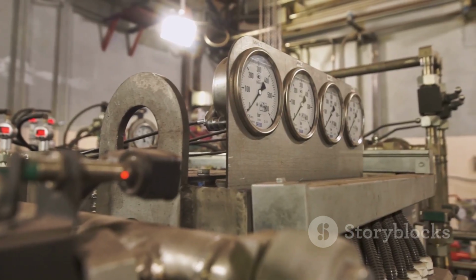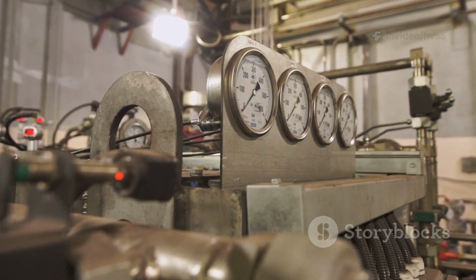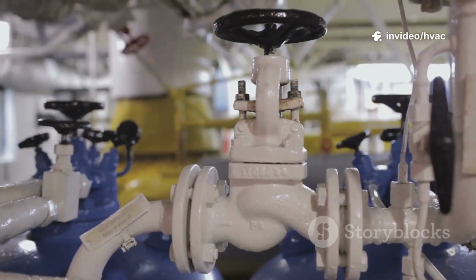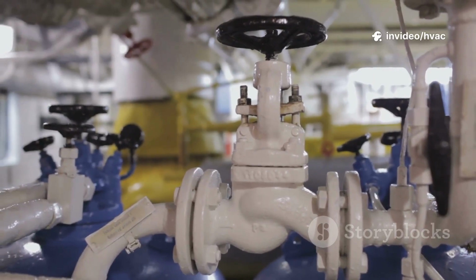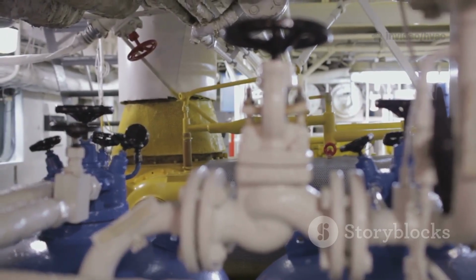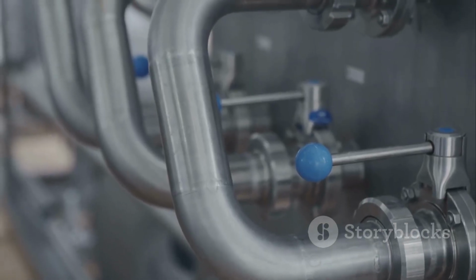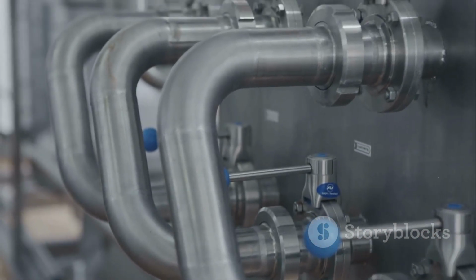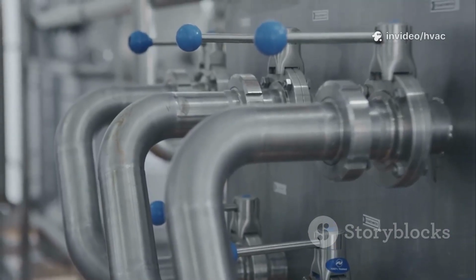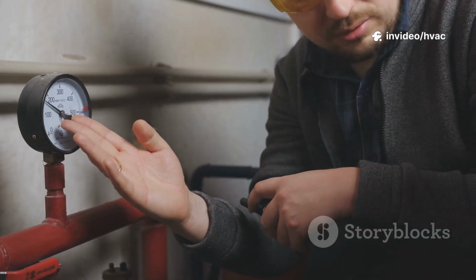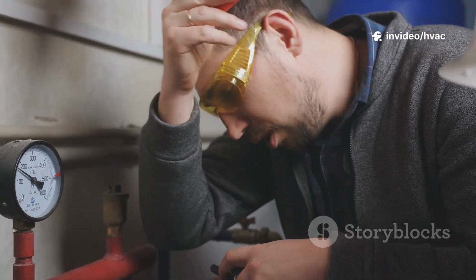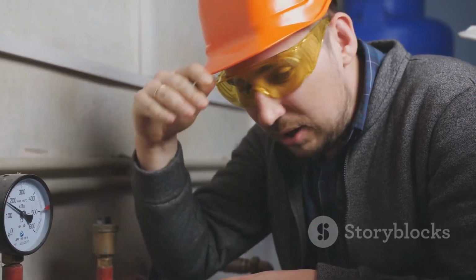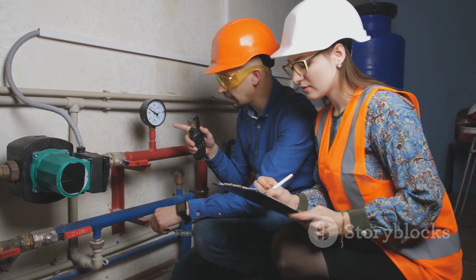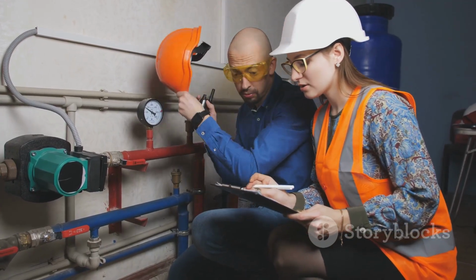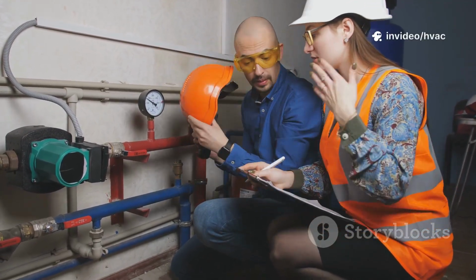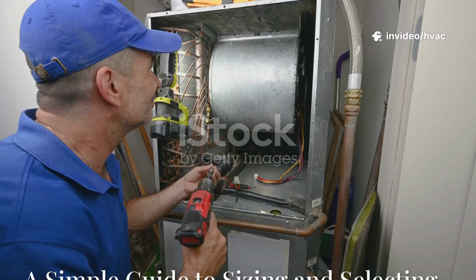Another factor to be aware of, though less critical for basic sizing, is the close-off pressure rating. This value tells you the maximum system pressure against which the valve's actuator can fully close the valve and hold it shut. This is important in high-pressure systems to ensure the valve can stop the flow completely when there is no call for heating or cooling. You must ensure that the pump head in the system does not exceed the close-off pressure rating of the selected valve and actuator combination. Checking these parameters, design flow rate, differential pressure range, and close-off pressure, will ensure you choose the right PICV for reliable and efficient operation.